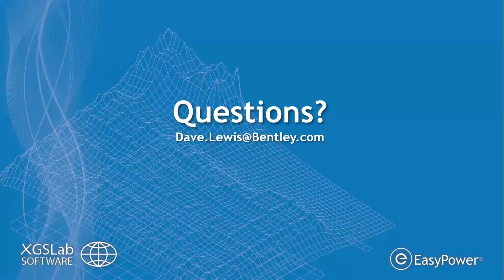If you're receiving or purchasing that information, you may be able to look to see if one of those strokes was within proximity of your equipment, whether it's a substation or a power plant, and that may kick off an evaluation. And of course, if you had an outage during a thunderstorm, that would be a very good case to look into some sort of maintenance procedures and inspection.